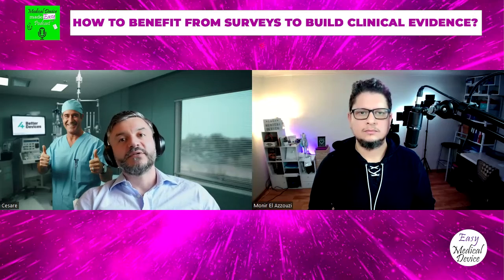This doesn't mean that, sorry, these are my kids ringing. This doesn't mean that it cannot be a clinical investigation. This depends on how you're going to perform this usability study. If you have to involve the patient and you have to do some burdensome procedure to prove the ergonomics of your device, then that could even become a clinical investigation. So this is what they're trying to say. And the same thing with surveys. Just because it's a survey doesn't mean that it cannot be a clinical investigation. So pay attention to that. Okay.